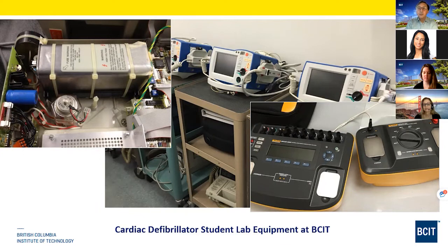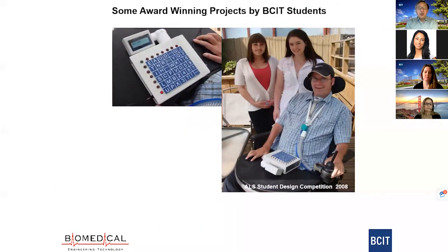They learn about the theory of operation, as well as in the lab, they will look at the output waveform, test the energy output to see whether or not it is according to specification, take the unit apart to look at the internal components, and then put it together and see whether or not it is still working after you take it apart. These are things that our students do in the medical device lab, and these are the things that a working biomed tech will do in the hospital in terms of making sure that these devices are safe and effective.